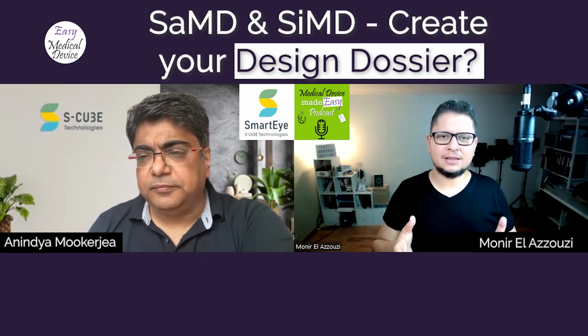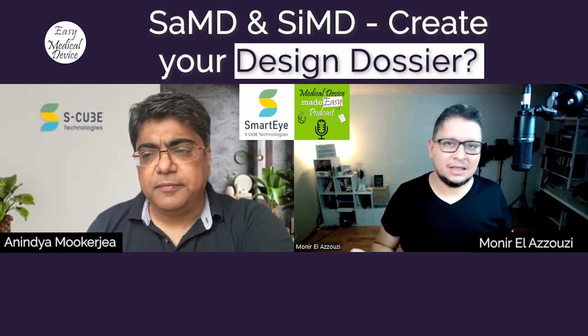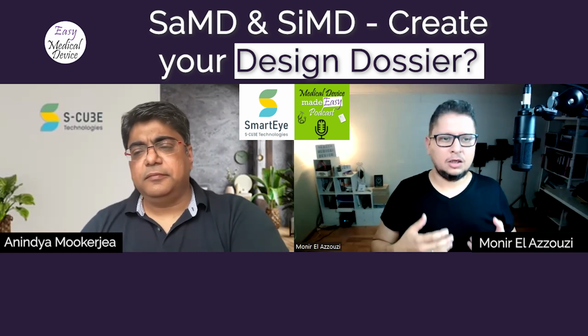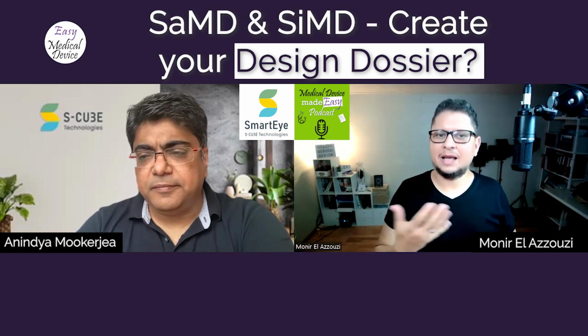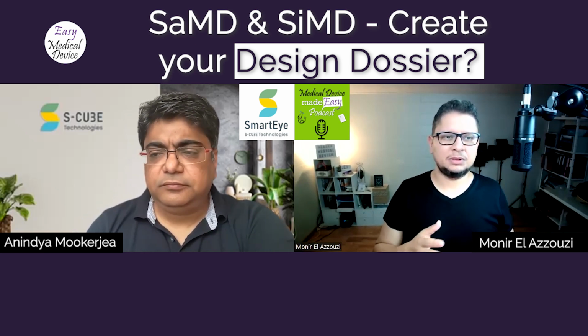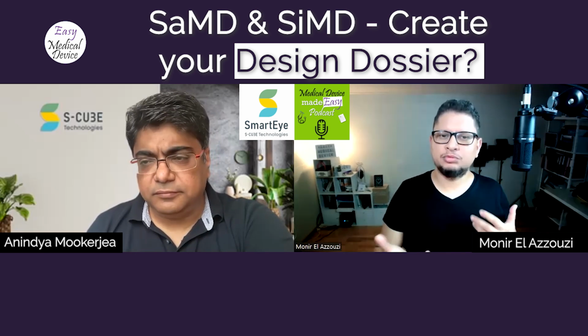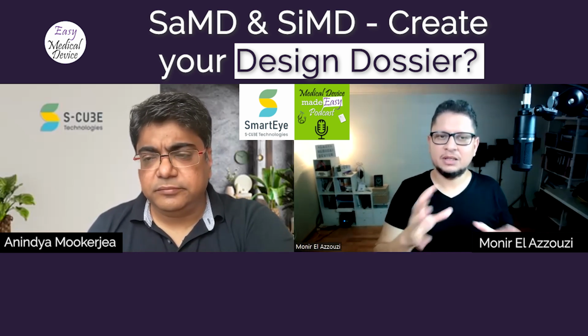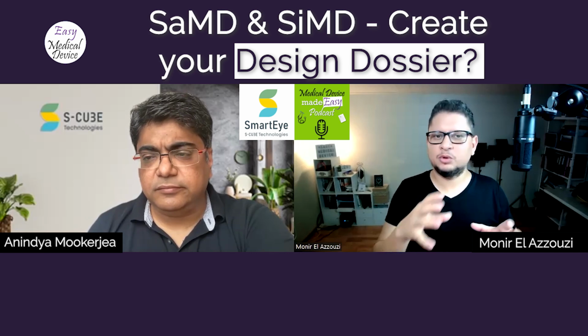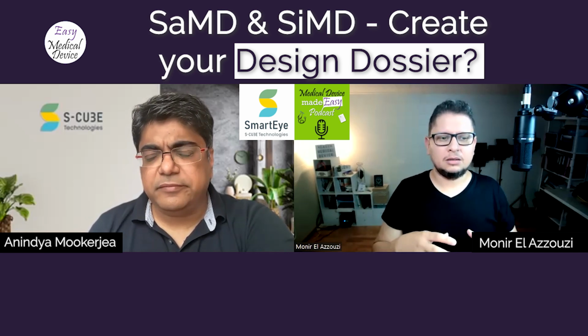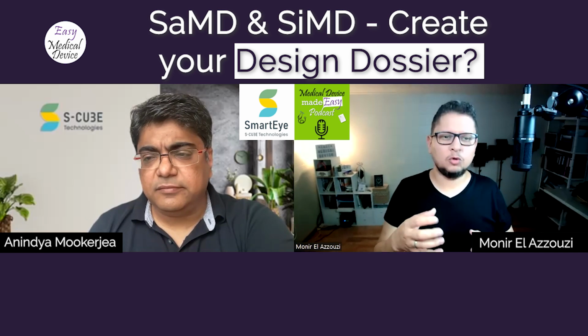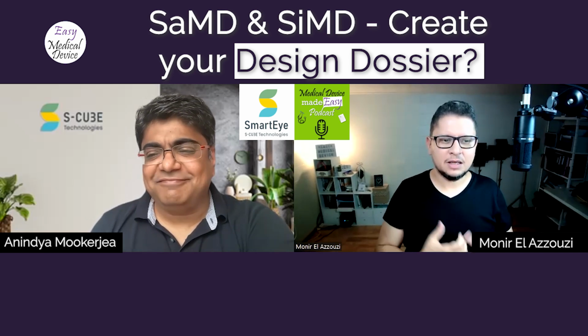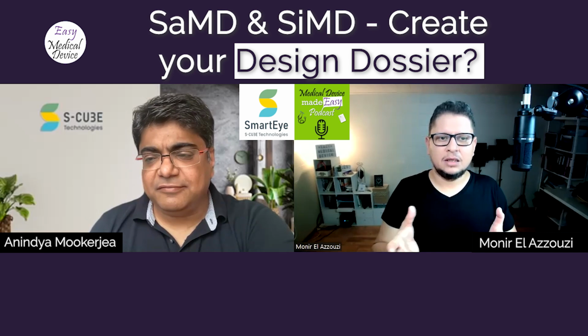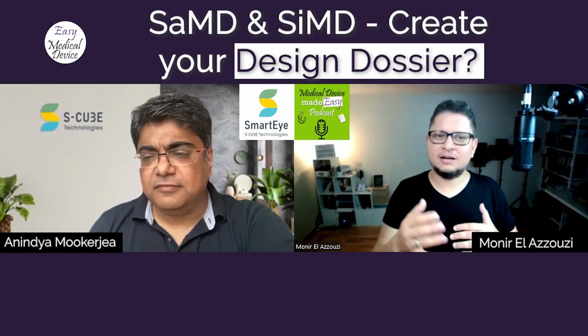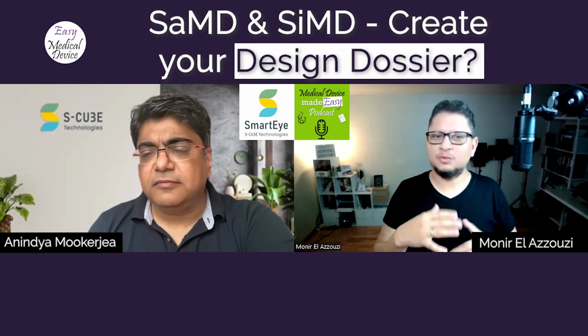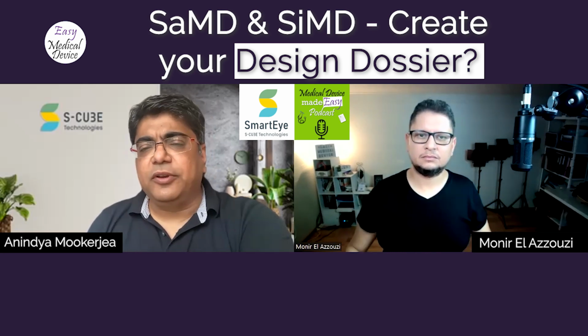So in terms of that, like any medical device development, you have to create a design file which shows people what the inputs, the outputs, the tests, the verification, and the validation are. Here, we talk about the waterfall process, but there is another term that we call the Agile process for development of a device. So in terms of the design file, can we say it's exactly similar to a hardware device, or are there really differences here? Great question, Munir.